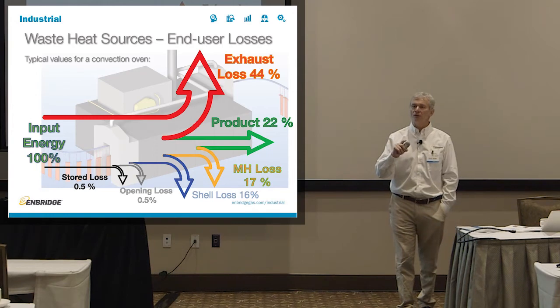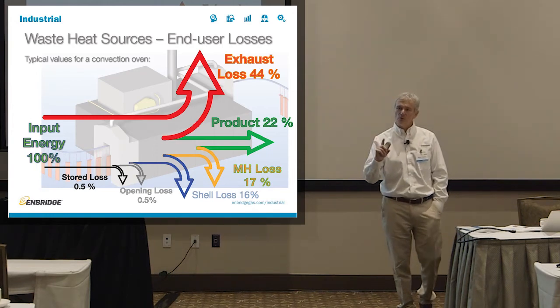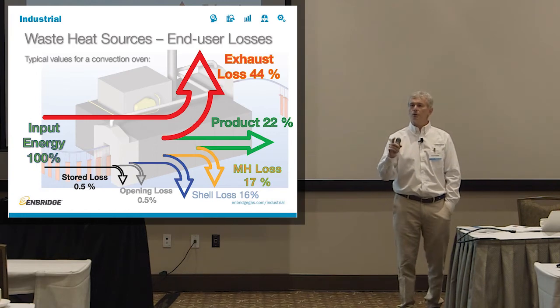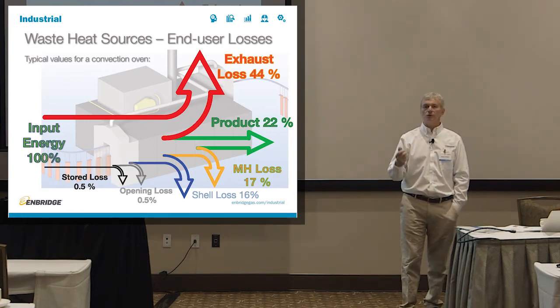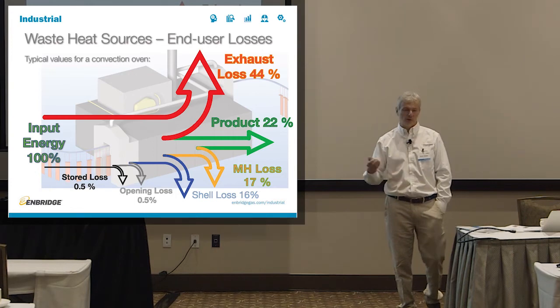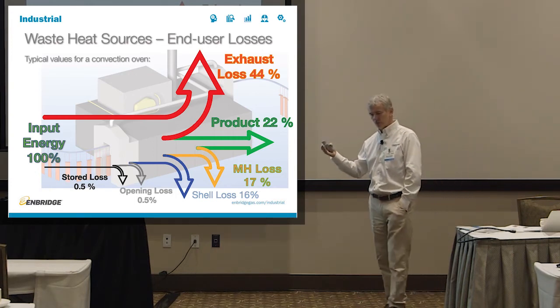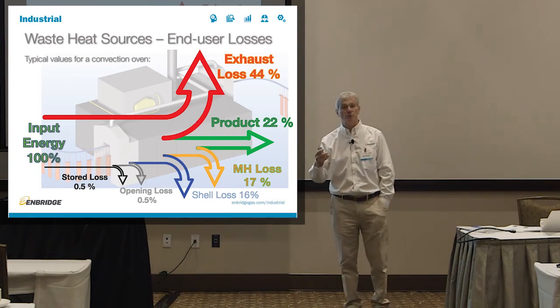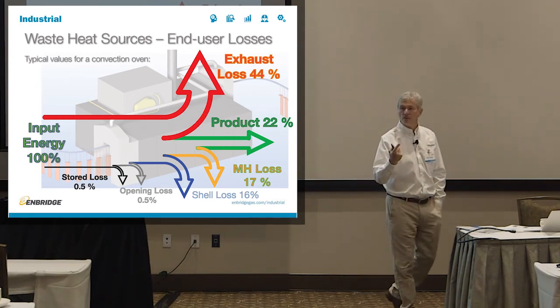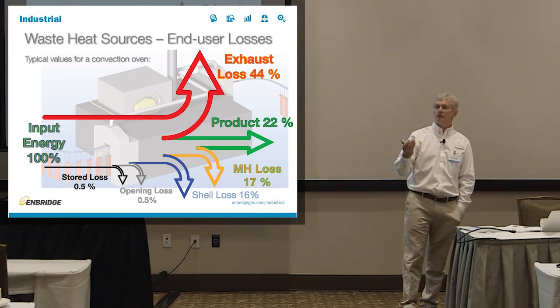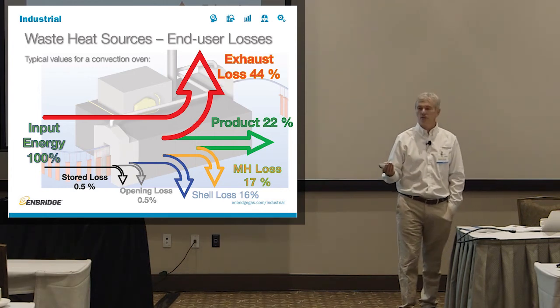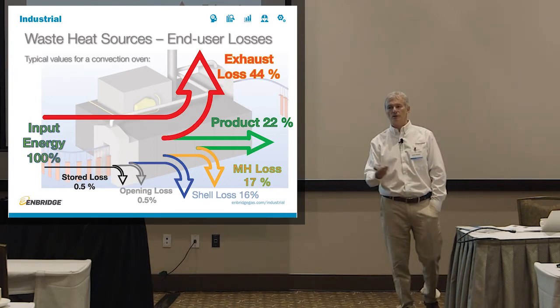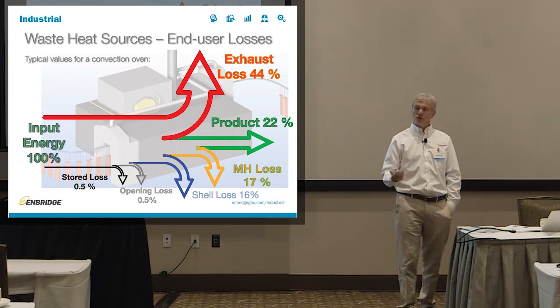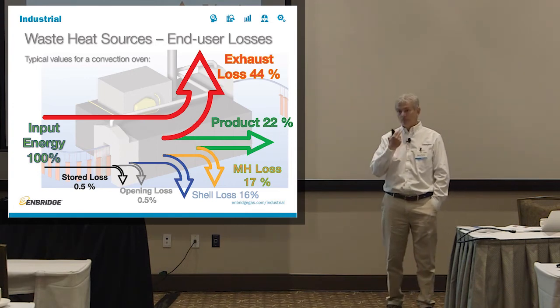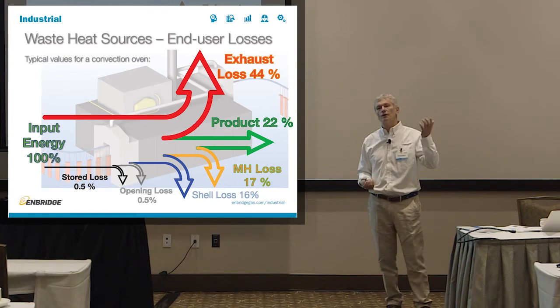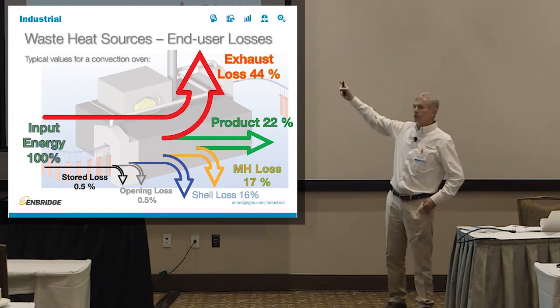So for those of you who have a convection oven, you will know that the critical part on the startup is something called purge. Because when you start the oven, you want to purge it as quick as possible. By TSSA standard, I think you have to have 4 times the volume of the oven purged before you can light up the burner. So for a sizable oven, that's a sizable amount of air. Nobody wants to wait for that for 3 hours. You're not going to call somebody in at 3 o'clock in the morning to start the oven for a 6 o'clock start. So you want it to be purged in 10, 15 minutes. But you didn't have a VFD, so now you're purging your oven all the time. That's where those exhaust losses are.